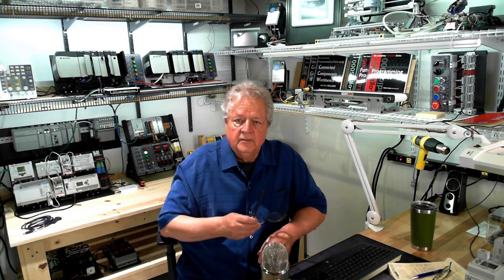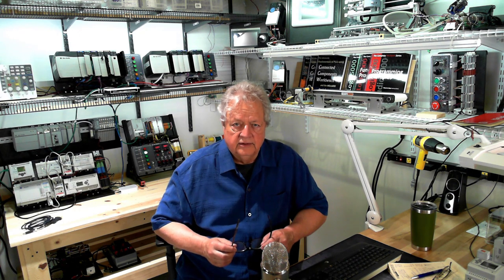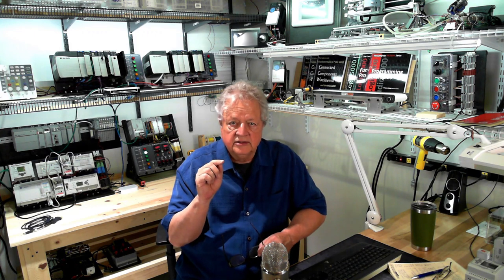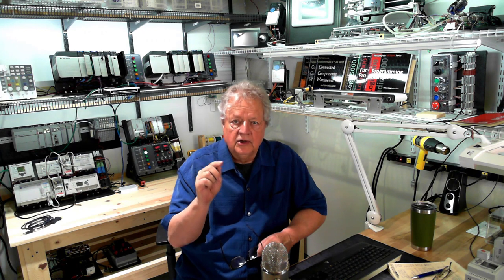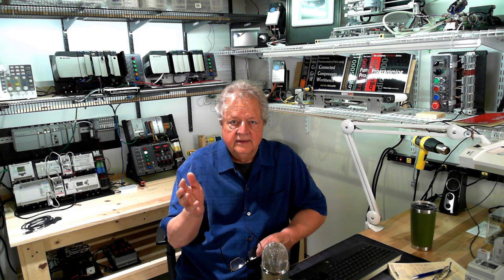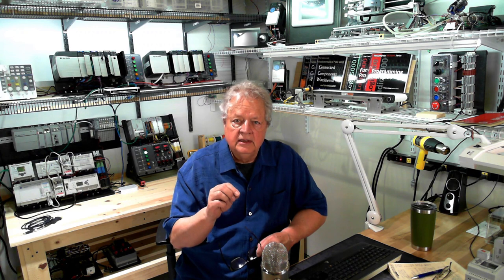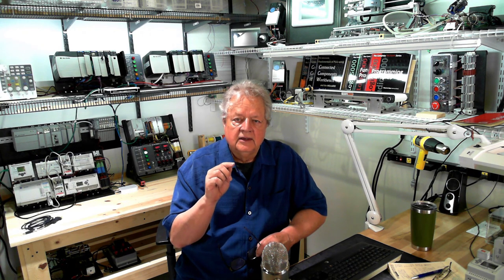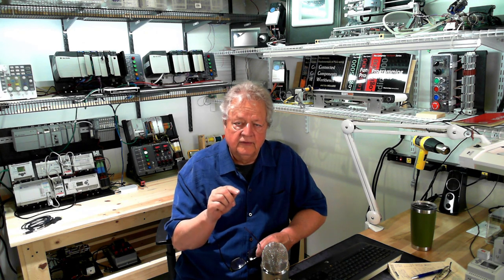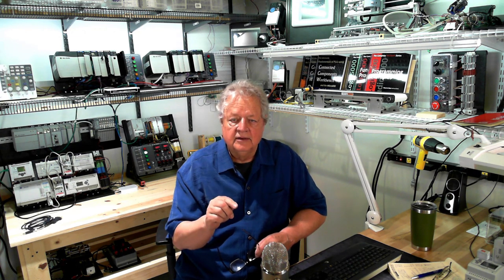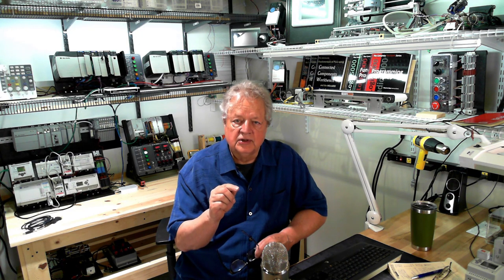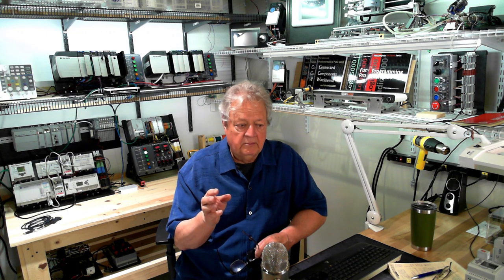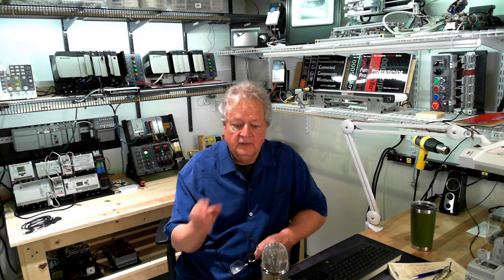Okay the takeaways from this lab project is the traditional start stop circuit. Momentary contact starts it. Momentary contact stops it. Now in the real world the stop button is wired normally closed. That way if a wire breaks it's not going to run. It fails to a safe position which means that the normally closed push button the stop push button is going to put a 24 volt DC voltage on the screw terminal for its input. Meaning that when the button is not pushed the input is on. So when you push the button the input goes off. So we did the traditional start stop circuit. You learned how to branch around and that concluded really the part A of this garage door opener. We'll see you for part B.